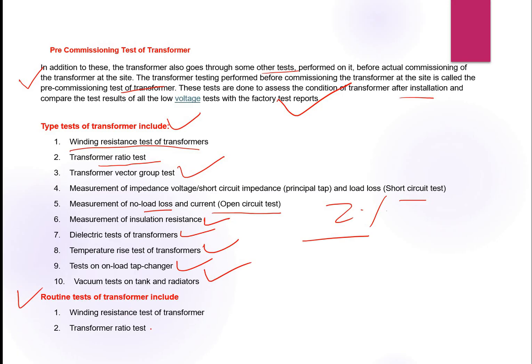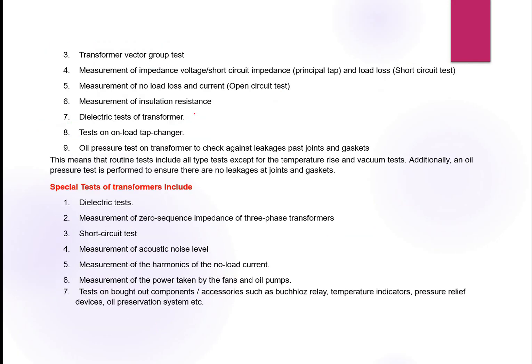And the routine tests are the winding resistance test, transformer ratio test, and vector group test. All tests are the same as the type tests, plus the dielectric test and the oil pressure test on the transformer to check leakage at joints and gaskets. This means that routine tests include all type tests except for the temperature rise and vacuum tests. Additionally, an oil pressure test is performed to ensure there is no leakage at joints and gaskets.